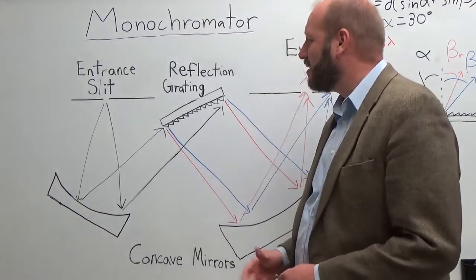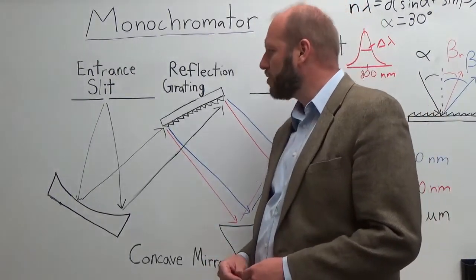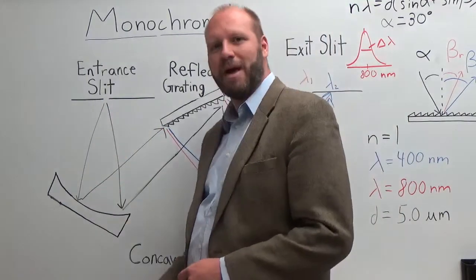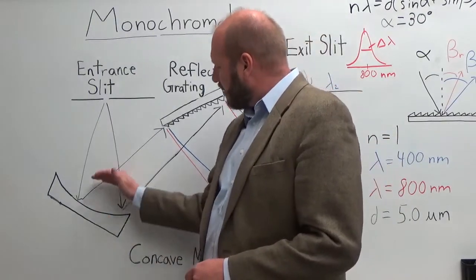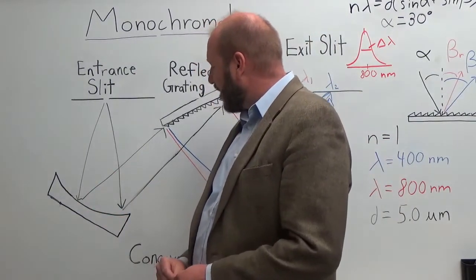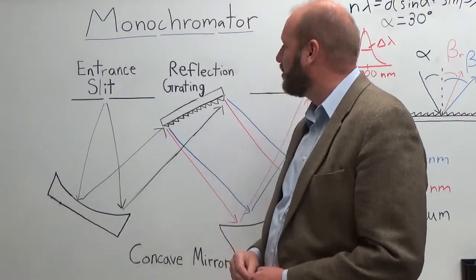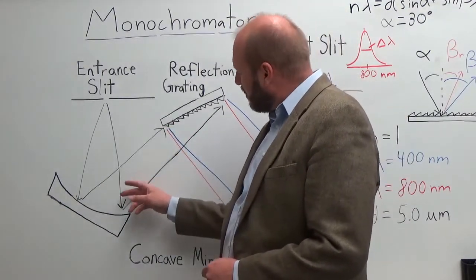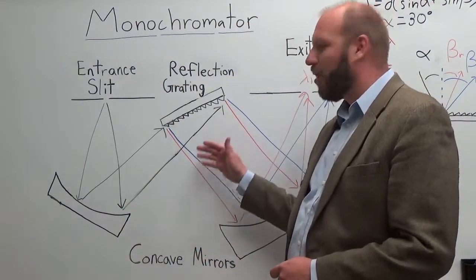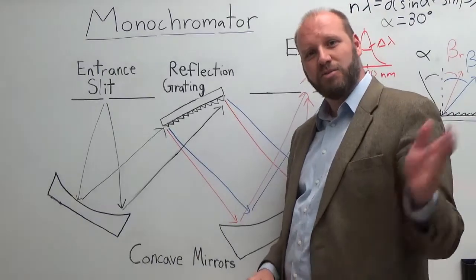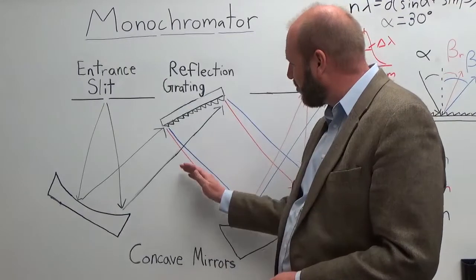A common monochromator design is the Czerny-Turner design that I have drawn here on the board. The Czerny-Turner design has an entrance slit where we let polychromatic light of many colors into our system. This then hits a concave mirror whose job it is to create parallel rays or collimated light that will then strike our diffraction grating. This light needs to be parallel so that it can hit our diffraction grating all at the same angle. Isaac Newton used the sun as his parallel light source when he did his original experiments on optics.